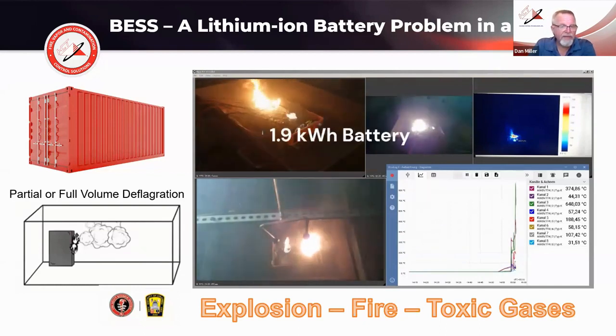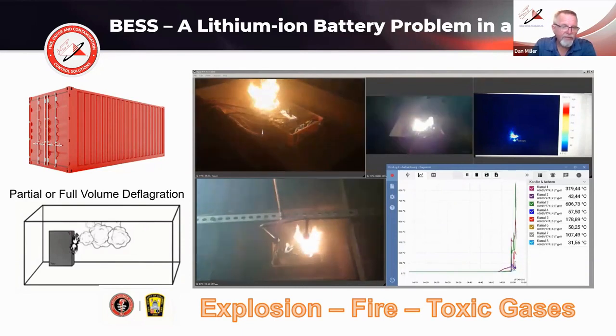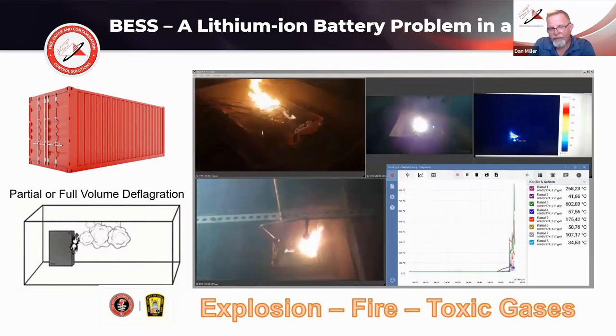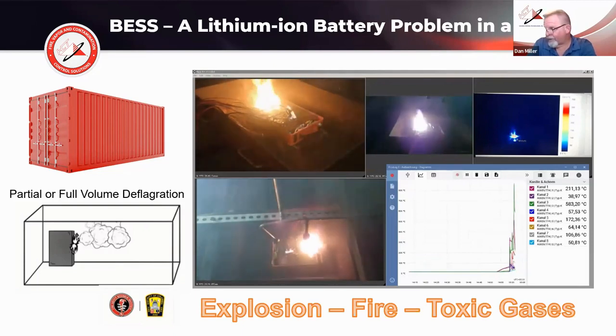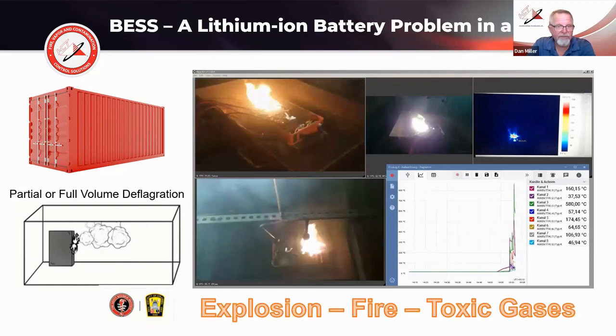The system is activated. The F500 at 3% goes onto the batteries. The batteries quickly go out as the encapsulator agent encapsulates and cools the electrolytes coming out of those batteries. As you'll notice, the fire kind of comes and goes as the different cells go into thermal runaway and start to spew the electrolyte out the ends.